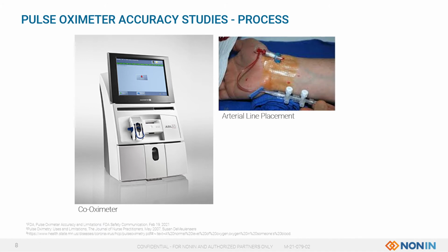And in order to get a blood draw, we place an arterial line in a subject along with connecting the subject to a pulse oximeter. We then take some readings with our device and compare them to the co-oximeter readings. For the average healthy adult, normal saturation can range from between 95 and 100%. However, for patients experiencing compromised respiratory function, their saturation can be much lower. And it is critical that pulse oximeters be able to read accurately in these situations.